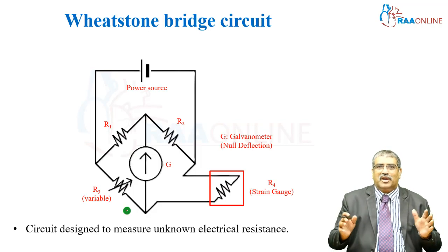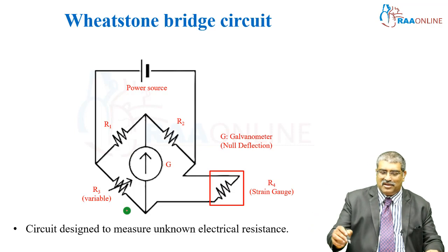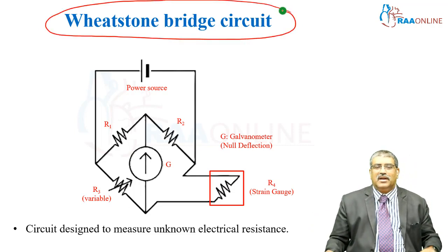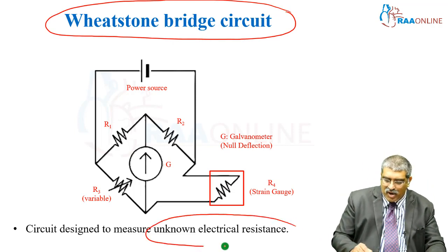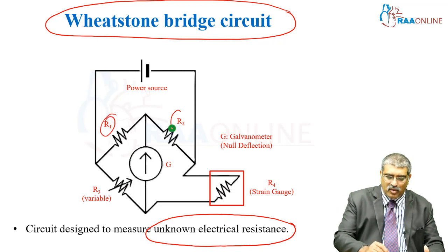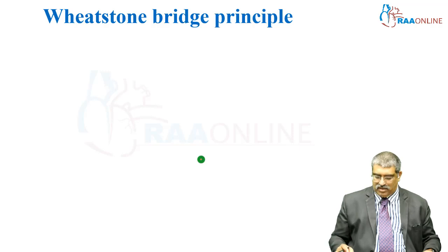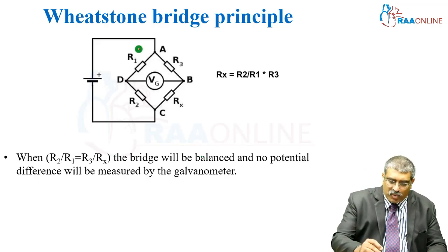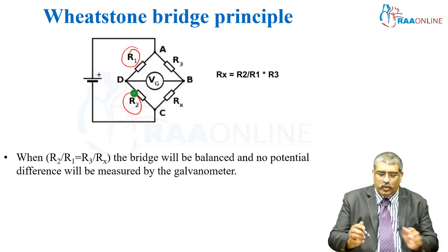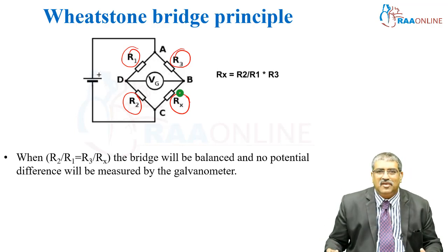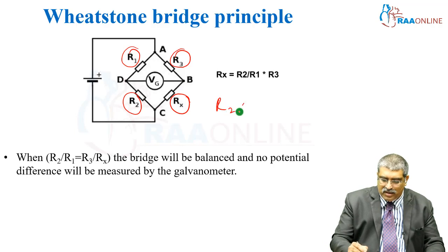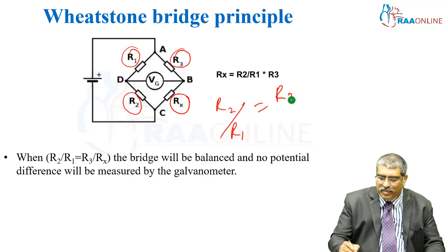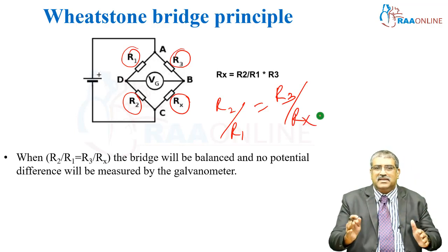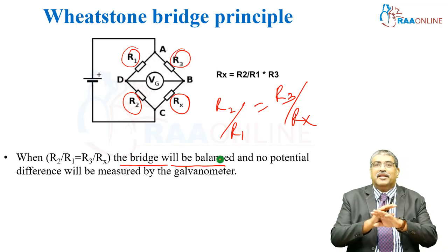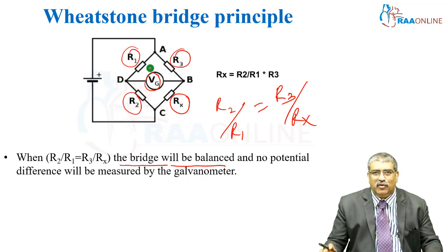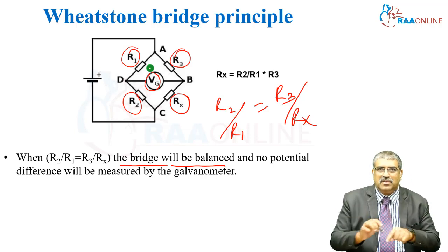Here comes the most important part. What is the principle behind arterial line monitoring, invasive monitoring? The first name that comes is the Wheatstone bridge circuit. This is a circuit to measure unknown electrical resistance. You have 4 resistances: R1, R2, variable R3 and the strain gauge resistance Rx. Here R1 and R2 are known resistances, and R3 is variable, to be matched to the unknown strain gauge resistance. When R2 by R1 is equal to R3 by Rx, the resistance on both sides of the bridge is balanced and there is no potential difference recorded by the galvanometer. This is the basic Wheatstone bridge circuit.